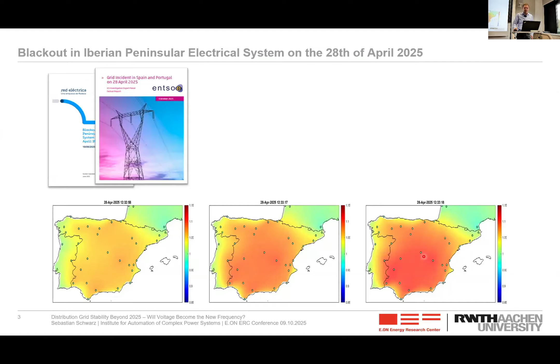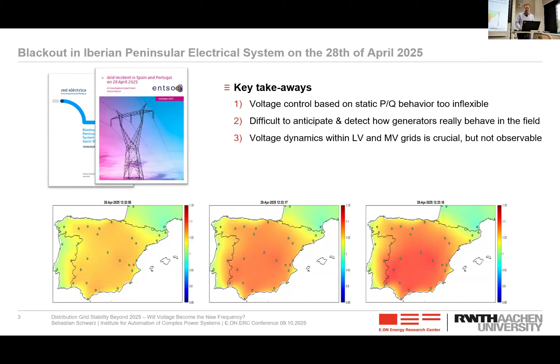The main takeaways from this incident are that in such extreme events, we see that voltage control based on classic static PQ might be too inflexible. It is difficult to see what devices are really doing in the field. Maybe they are following grid codes on paper or in the lab, but we don't know how they really behave under operational conditions. And of course, it is unfortunate that we do not have the capability to observe what is going on in low voltage and medium voltage.